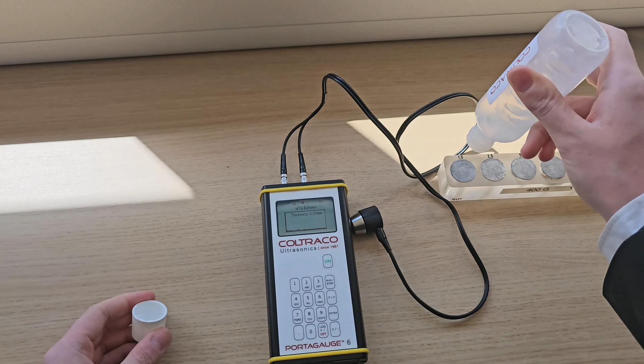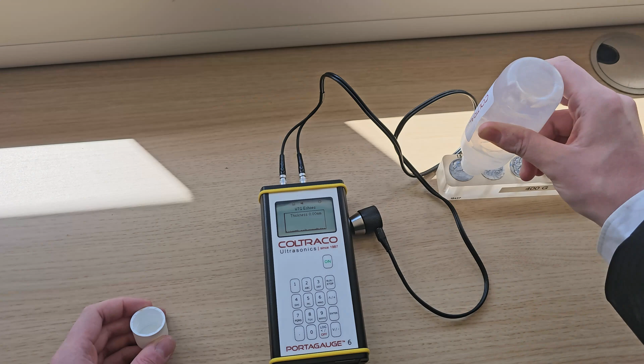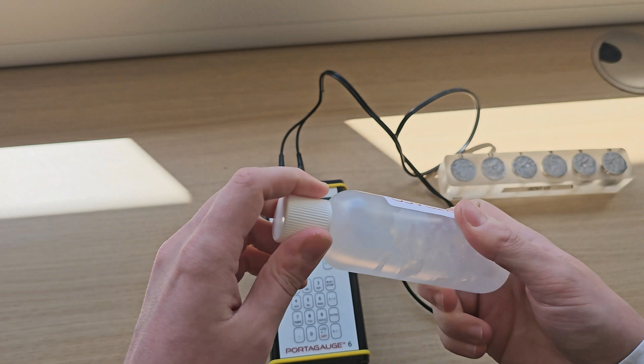So next I'll place a small amount of gel on each of these test pieces here. So the purpose of this gel is just to ensure that we have good contact with no air gaps between the sensor and the material that we're testing. So I've just placed a small amount of gel on each of these here, and we'll see as I in turn place the sensor on, starting with 1.5mm.